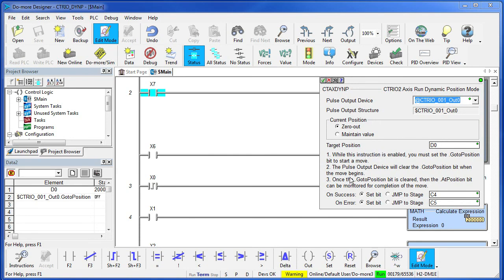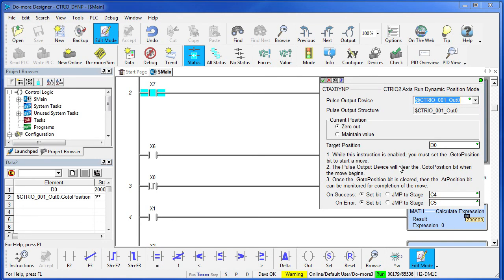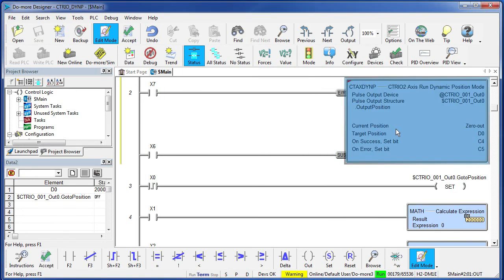These little reminders are telling us that once this instruction is enabled you have to set the dot go to position bit to start the move. We'll see that in just a second. This instruction will clear that bit when the move begins and once it does you can go set it again to change the destination.